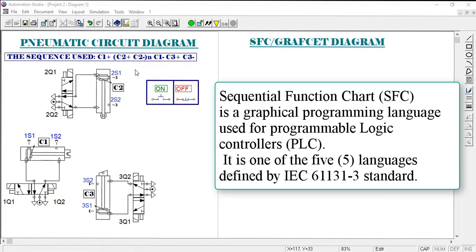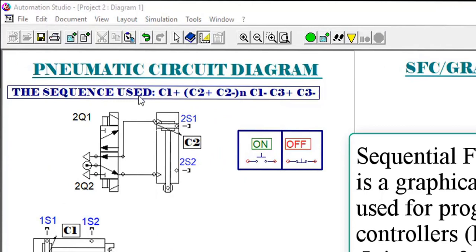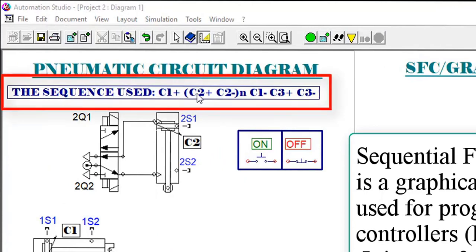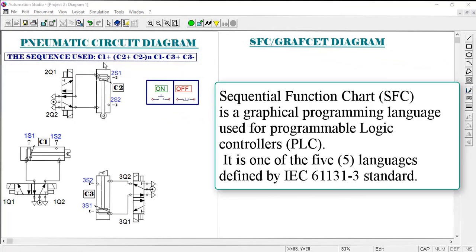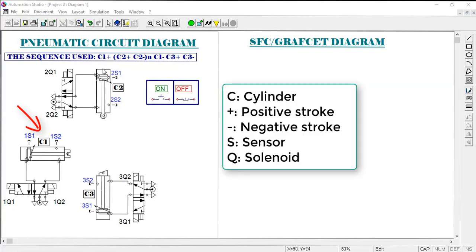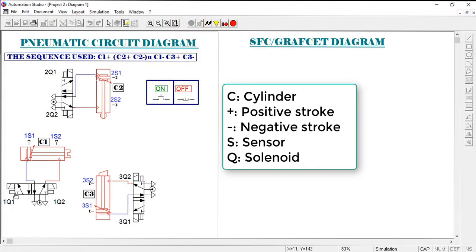Let's turn this sequence into an SFC program using Automation Studio. SFC stands for Sequential Function Chart — one of the five languages a PLC can be programmed in. The sequence is: C1+, C2+, C2-, C1-, C3+, C3-. Here, C1+ means the first cylinder goes into extension — plus means positive stroke, which is extension.